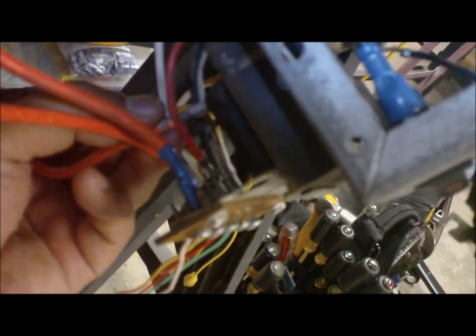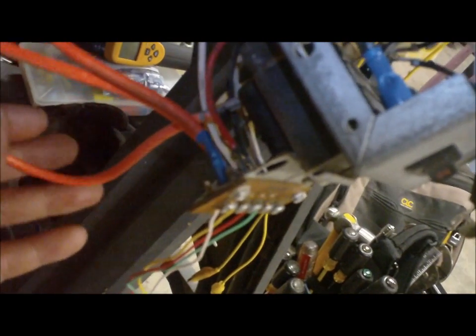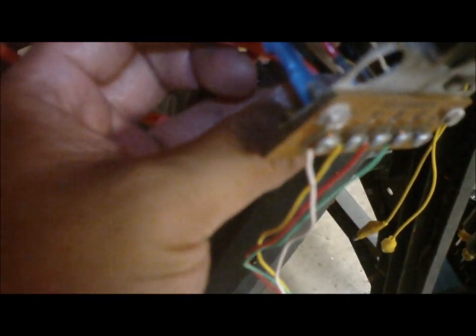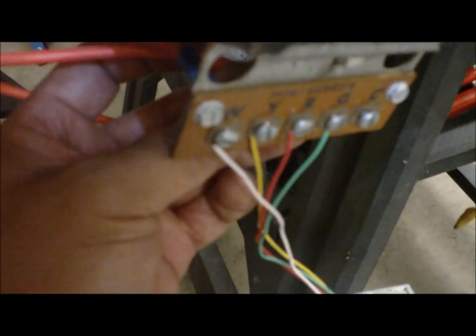That's from the bottom wire from the fan limit switch low voltage side. And now we're gonna follow the wire coming from the top which is this one right here. Follow it down to see where it is connected and this wire right here is connected to your low voltage terminal board on the R.